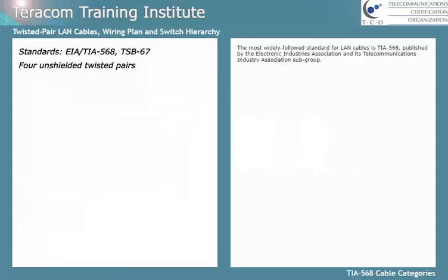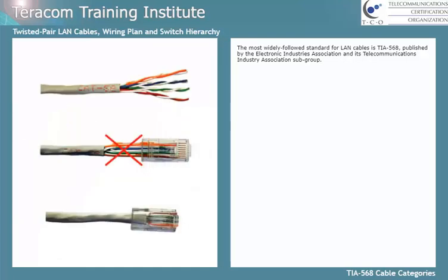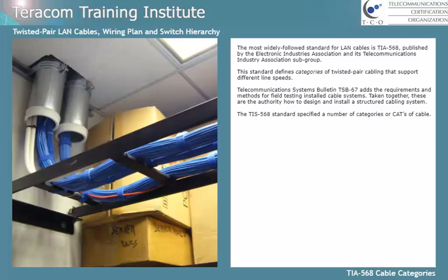The most widely followed standard for LAN cables is TIA 568, published by the Electronic Industries Association and its Telecommunications Industry Association subgroup. This standard defines categories of twisted pair cabling that support different line speeds. The Telecommunications Systems Bulletin TSB 67 adds the requirements and methods for field testing installed cable systems. Taken together, these are the authority on how to design and install a structured cabling system. The TIA 568 standard specifies a number of categories, or cats, of cable.